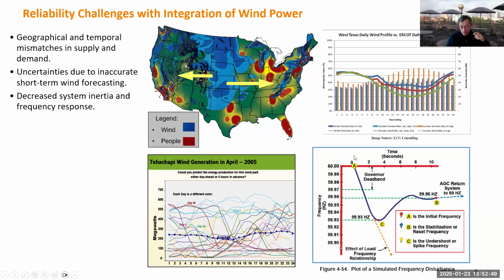When you have a coal-fired power plant, because it has a very large rotor, it has inertia, which means if you have a disturbance near that power plant, the rotor will take some time to speed up or slow down. For example, if you suddenly lose a load, the frequency will go up. If you suddenly trip a generator, the frequency will go down. The frequency change will not be fast if you have inertia. But when you replace the conventional generation by wind power generators, those generators have lower inertia or no inertia. If you have a fully power electronics inverter connecting the wind turbine generator to the grid, inertia will not be added to the transmission grid. So when the inertia decreases, the frequency will drop much faster.